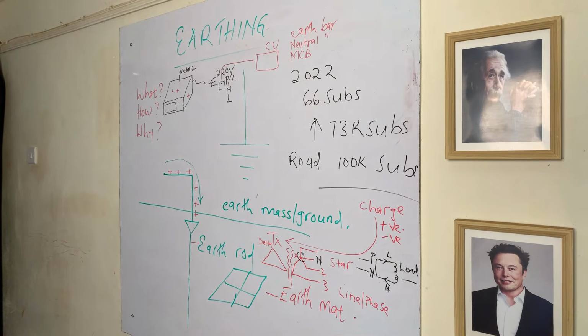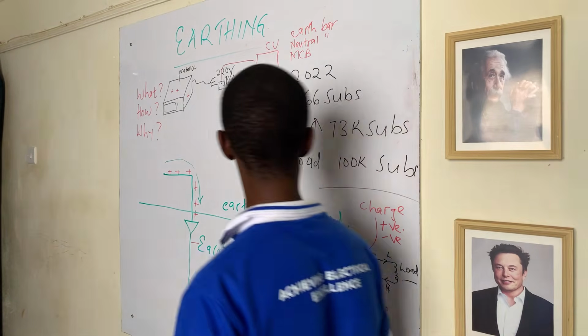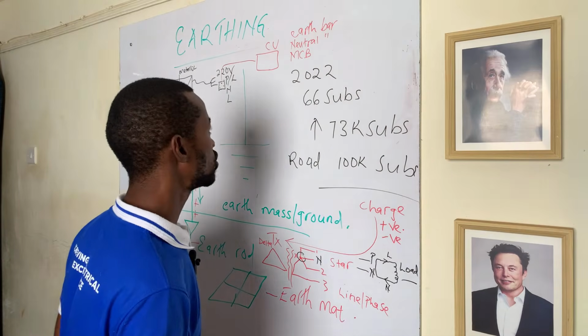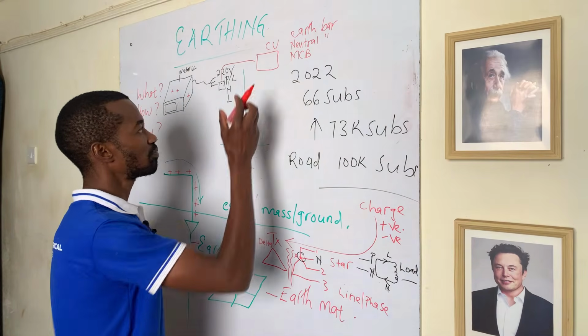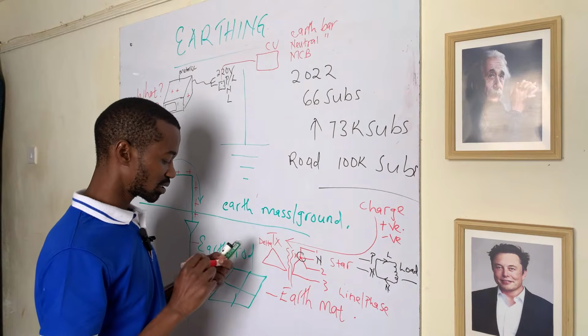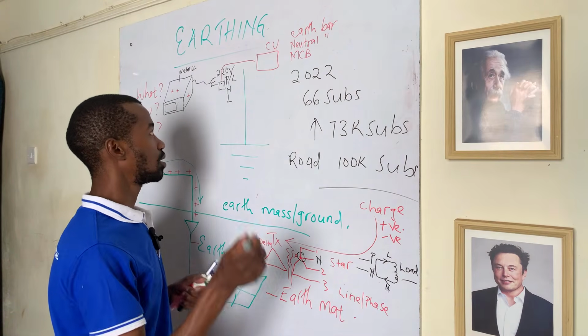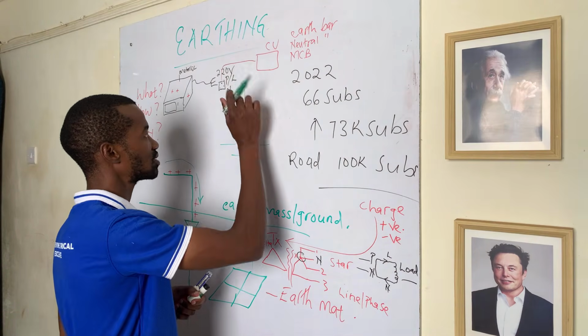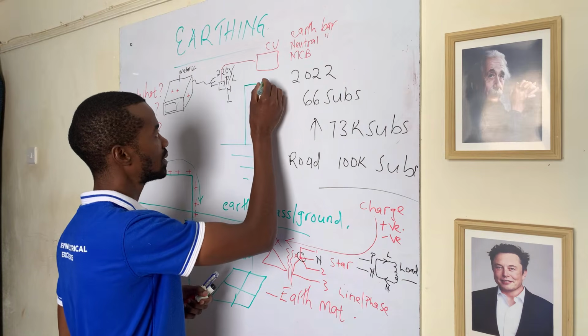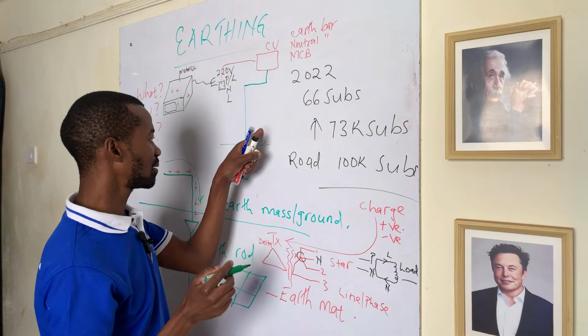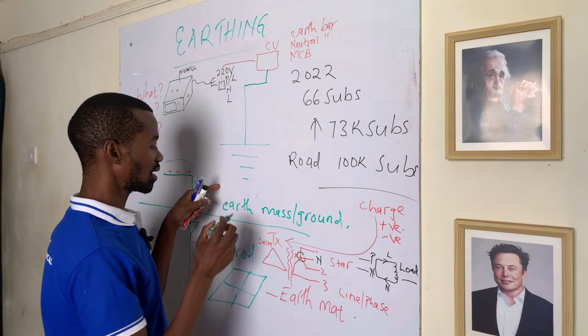Apart from getting all the way to the consumer unit, what we need to be sure about is that from the consumer unit, the continuity of the earthing has to go all the way to the meter board, and then from the meter board, it has to go to the earth rod.